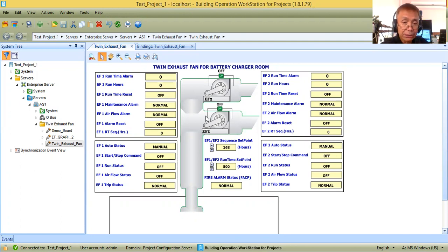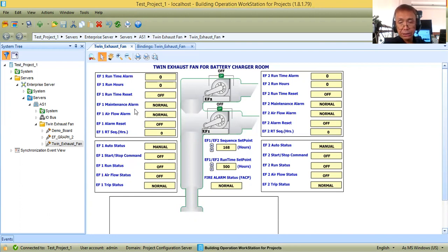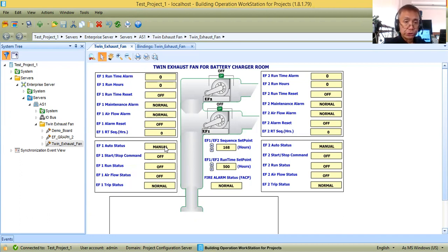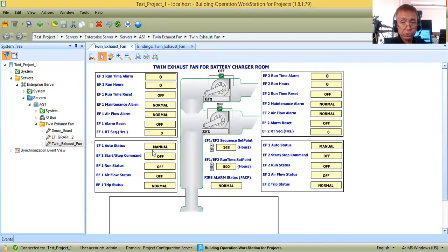Today I'm going to show you how to bind all these points. I have software points here: runtime alarm, run hours, runtime reset, maintenance alarm, airflow alarm, alarm reset, and sequence time. I also have physical points — these monitor real-time values from your motor control, such as whether it is in automatic mode and whether there is airflow from the air differential pressure switch installed across the fan.